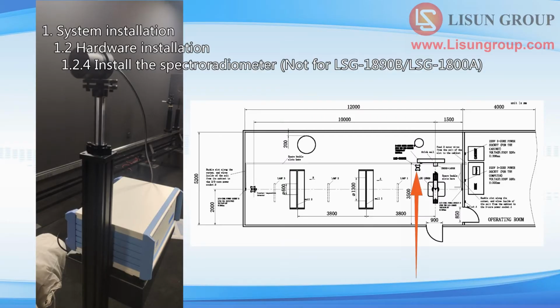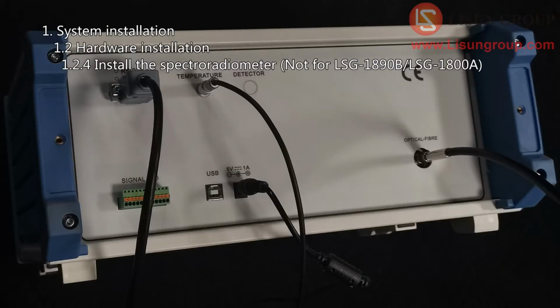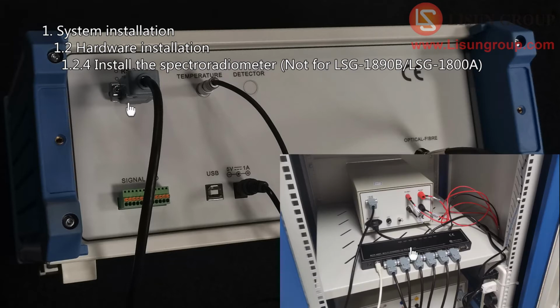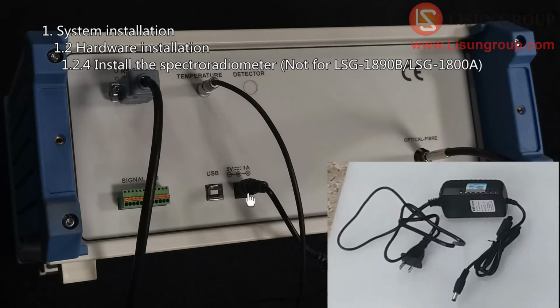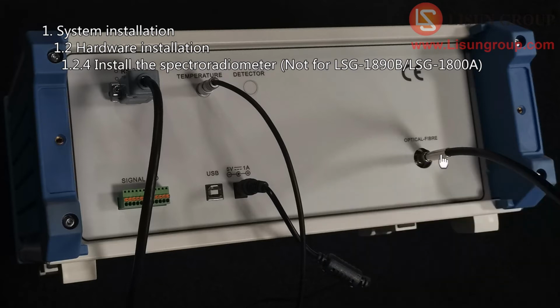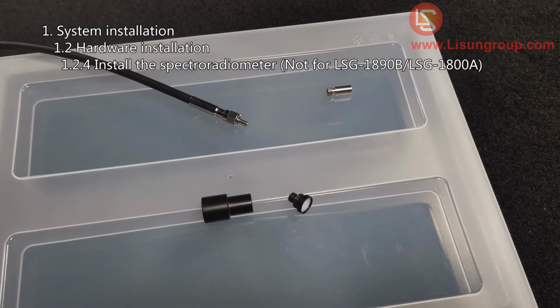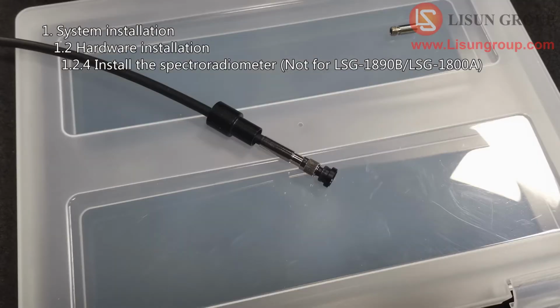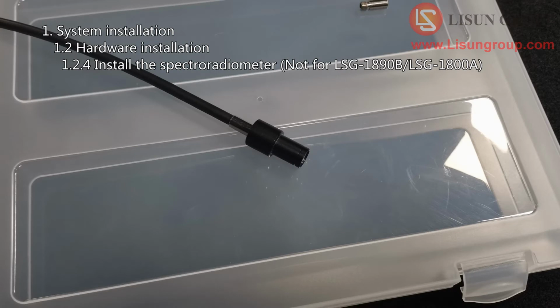Put the spectroradiometer and its holder at the correct position according to the drawing. There are 3 wires that need to be connected for the spectroradiometer. The RS-485 communication cable is connected to the communication box inside of the cabinet. The power adapter. The optical fiber. The other end of the optical fiber needs to be assembled with the sleeves. Please assemble as shown in the figure.